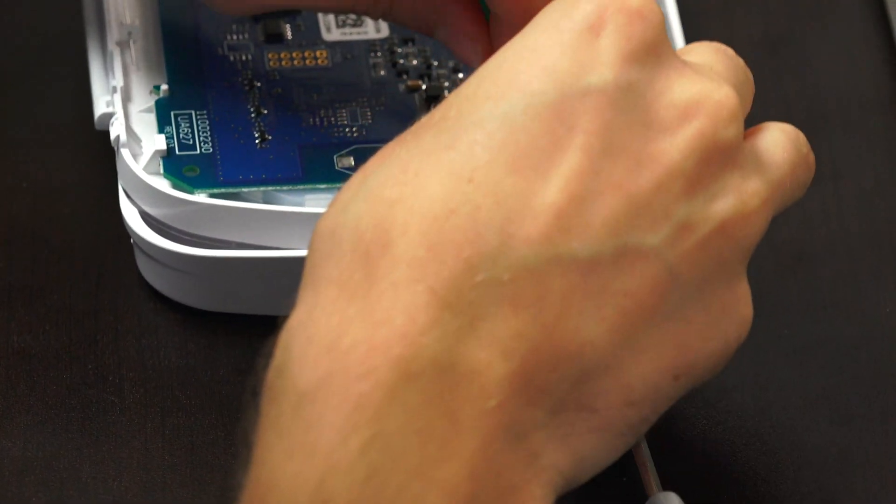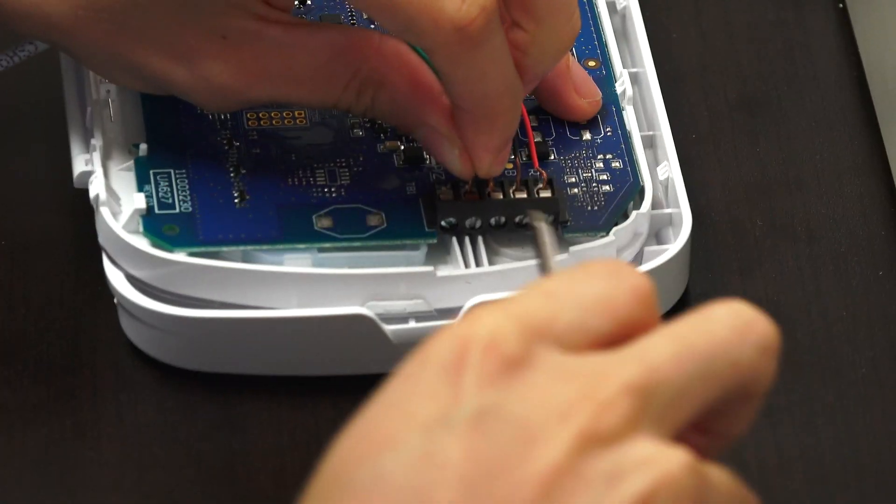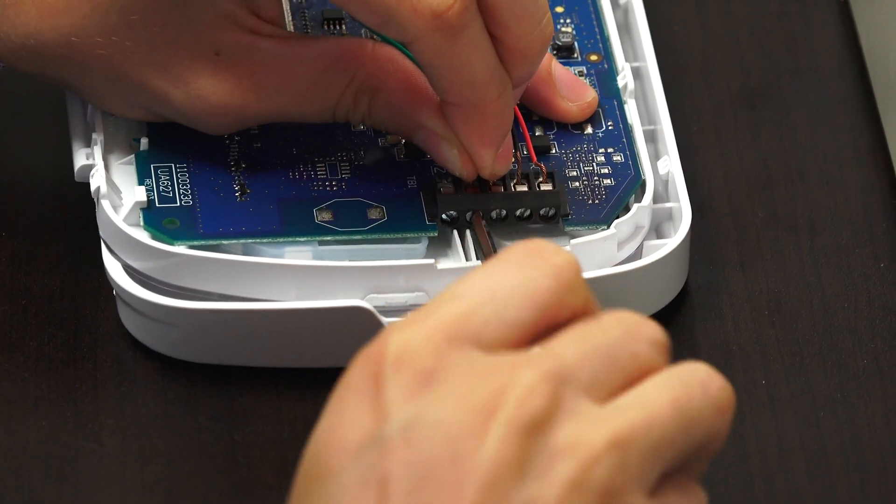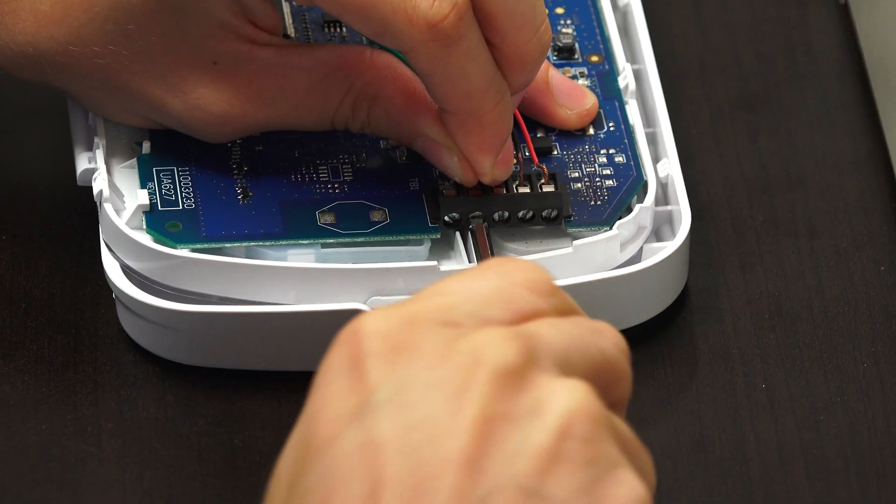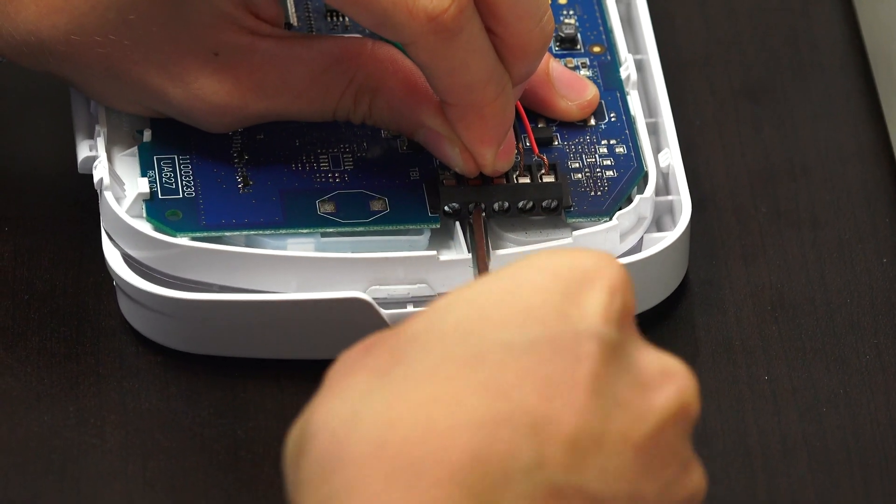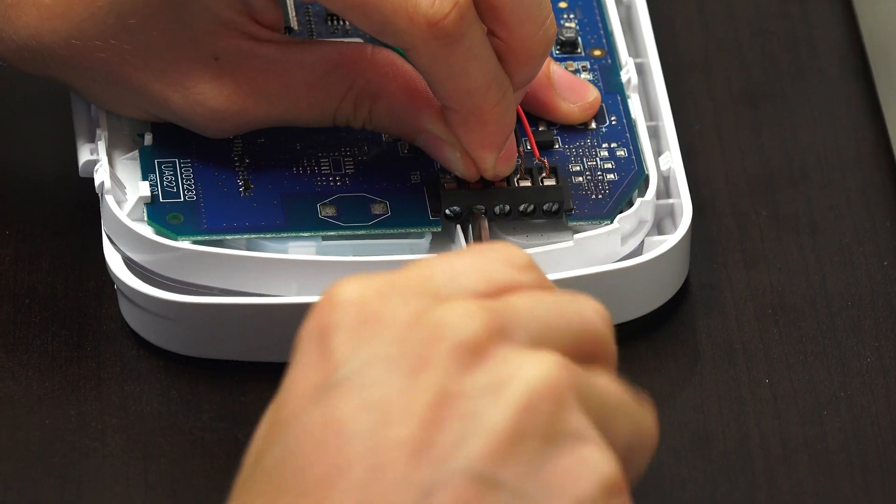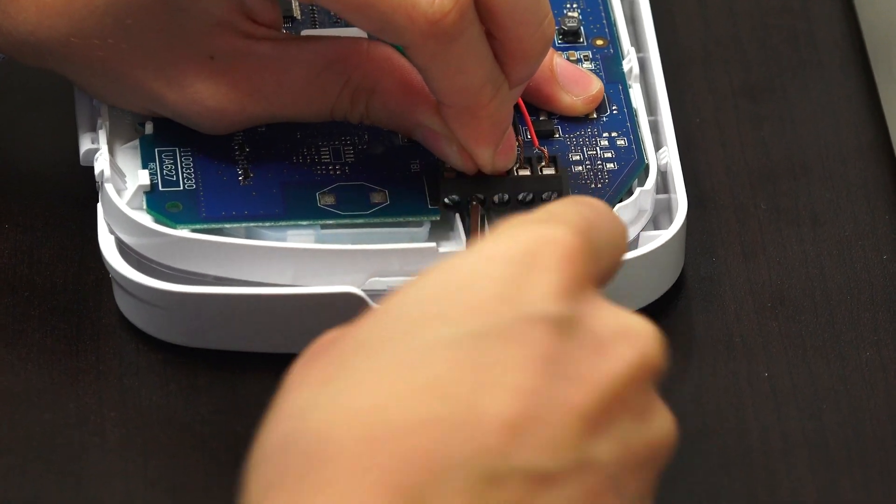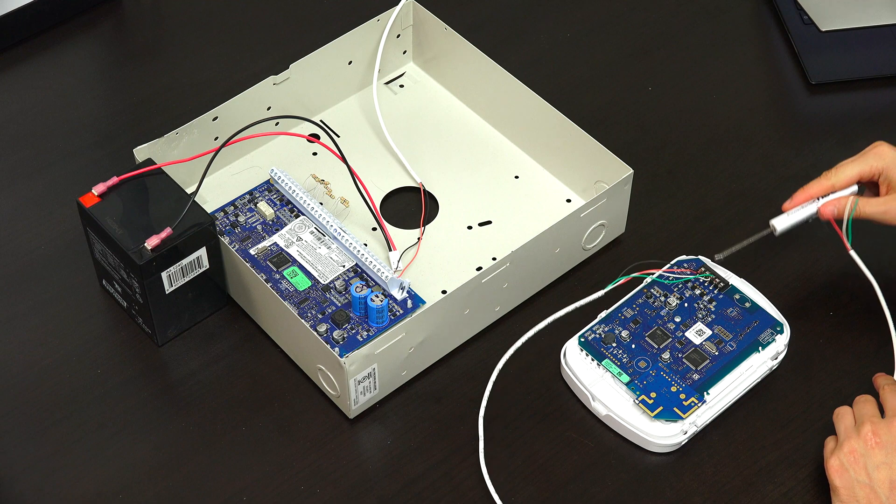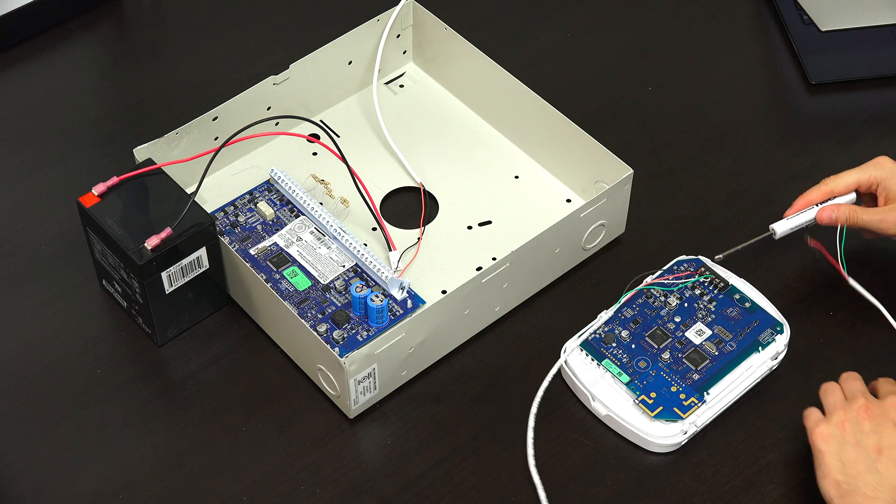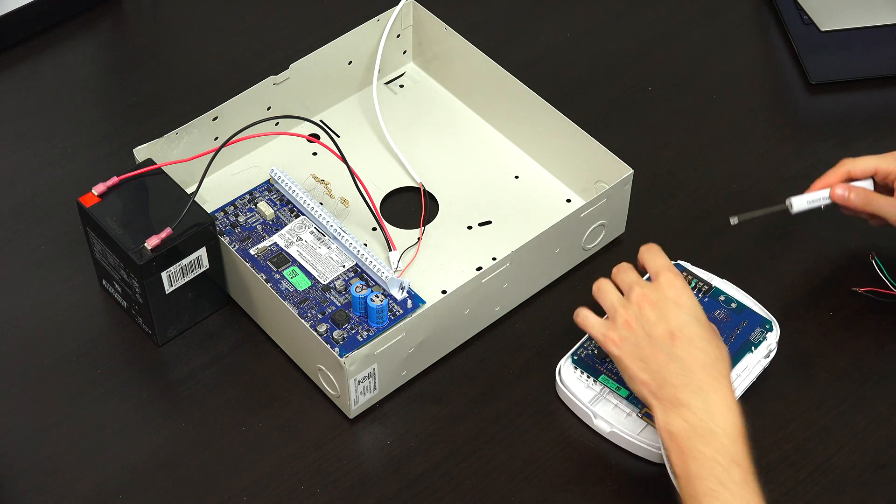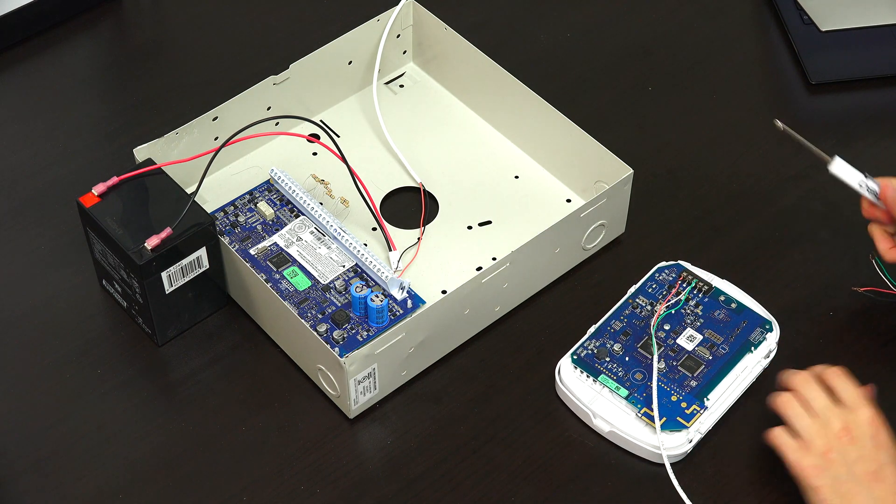The yellow or white and green wires are for the data connections with the panel. That's how it communicates. The red and black wires are for power. Really, color doesn't matter as long as everything is going to the proper spot. So we have completed our connections here. Give it a quick tug. They're nice and secure.